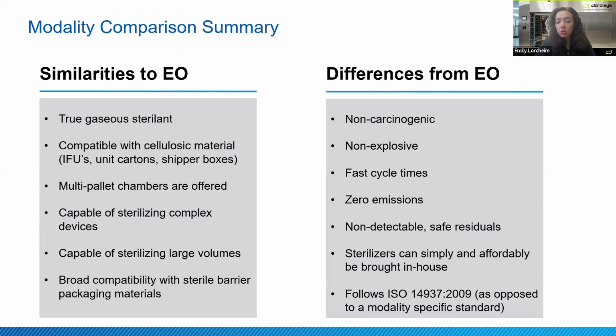Differences, again: non-carcinogenic, non-explosive, very quick cycle times, zero emissions, non-detectable safe residuals. You can have sterilizers brought in-house, or we can do contract sterilization at our ClorDiSys facilities, and we can even convert ethylene oxide chambers to chlorine dioxide chambers. Now we follow ISO 14937, which is different from the ethylene oxide standard. However, again, very similar process.